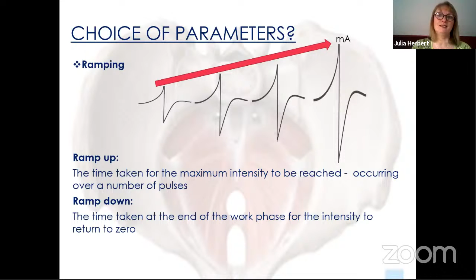You can also do the same at the end of a contraction. So a lot of programs will be set at about 1 second in clinical practice. Myself, I will use half a second, because 1 is quite a long time to get there. So as long as the patient's not very oversensitive to stimulation, I would tend to set that at 0.5 of a second clinically.